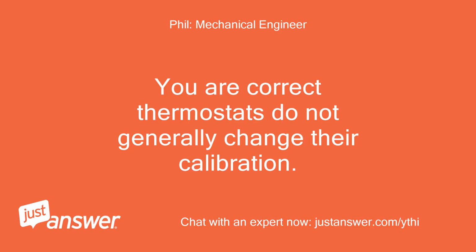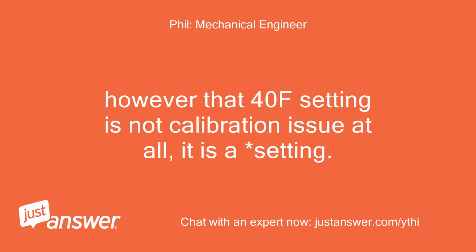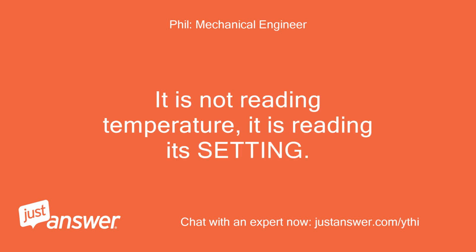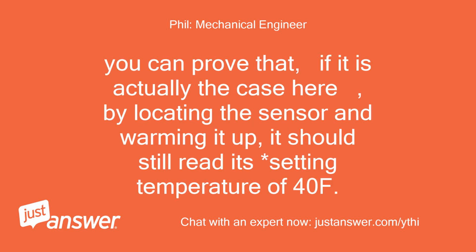You are correct, thermostats do not generally change their calibration. However, that 40F setting is not a calibration issue at all, it is a setting. Someone set it at 40F. It is not reading temperature, it is reading its setting. You can prove that, if it is actually the case here, by locating the sensor and warming it up; it should still read its setting temperature of 40F.